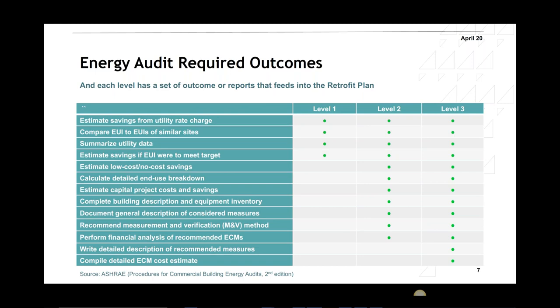Energy audit required outcomes. Each level has an outcome. So for a level one, you need to estimate savings from utility rate charge. If that's the case, and here, let's say in Dubai, that would not be applicable. Compare EUI to EUIs of similar sites. Definitely you have to do that. Summarize the utility data, maybe in an Excel spreadsheet, put it in a report, and estimate savings if EUIs were to meet targets. So level one is very, very brief. You would just put ideas of things that need to be changed. Normally you're just testing the water to see if there is a potential or not. Most people go with a level two audit because it's more robust.